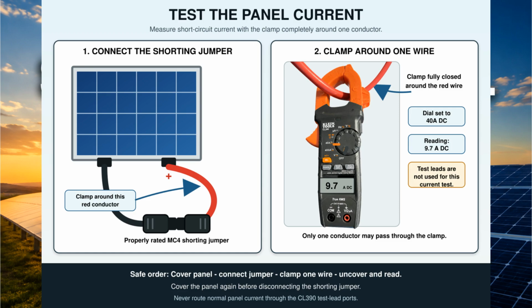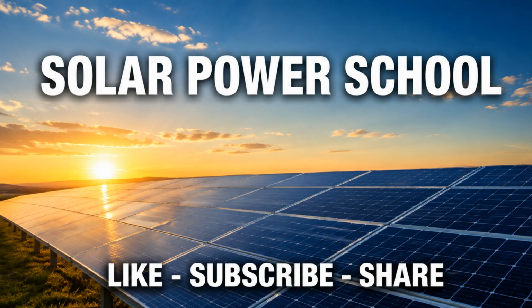When the test is finished, cover the panel again and confirm that the current reading has dropped before disconnecting the jumper. Do not separate MC4 connectors while current is flowing. Now you know how to perform the two basic checks on one solar panel. Read the label, measure VOC with the meter leads, and measure ISC with the clamp completely around one conductor.